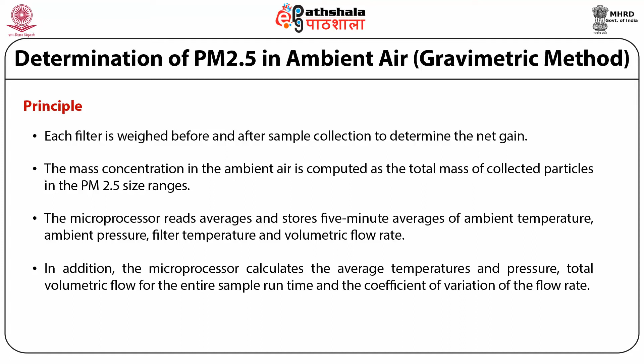The microprocessor reads, averages and stores 5-minute averages of ambient temperature, ambient pressure, filter temperature and volumetric flow rate. In addition, the microprocessor calculates the average temperature and pressure, total volumetric flow for the entire sample runtime, and the coefficient of variation of the flow rate.